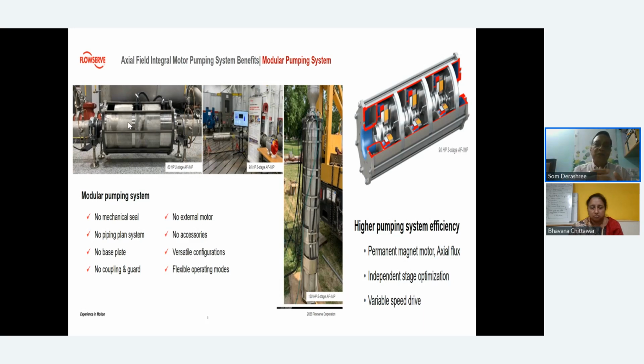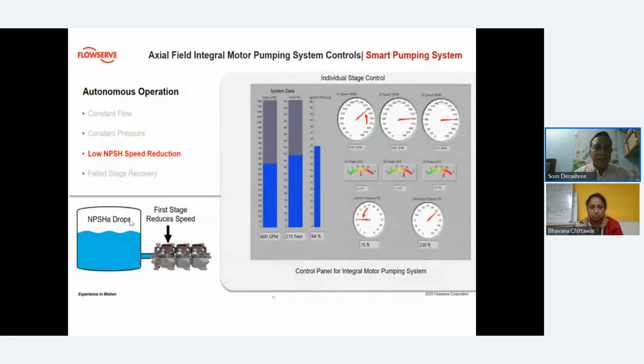Yeah, the limitation is that because the motor is also inside, you cannot have more than 90 degrees. Otherwise, you'll have to have a separate cooling arrangement, etc. But this is a multi-stage propeller system that they have come up with. What happens is NPSH has dropped actually, and this is now going to stop. So what you do is you VFD, this reduces, but then this will increase because it already has that additional head required, and the cavitation can be avoided. And each of these stages can be monitored in terms of the GPM it is having, and the head that it is developing, and all that.